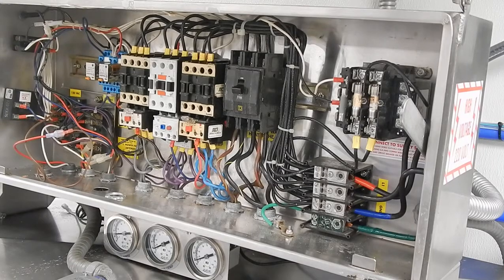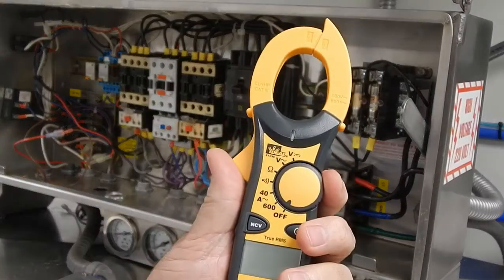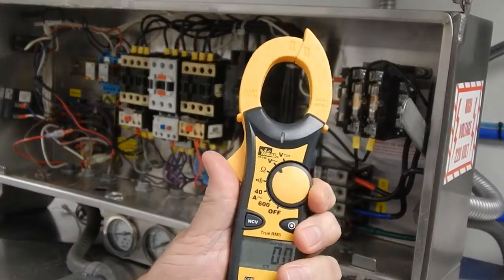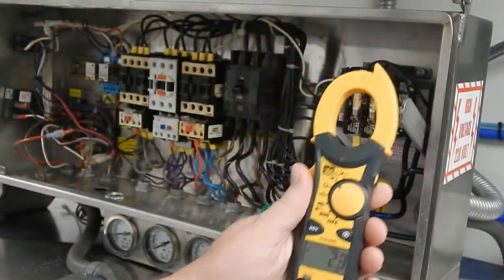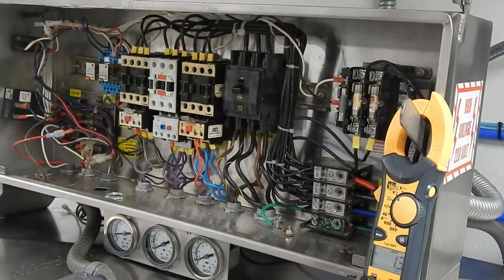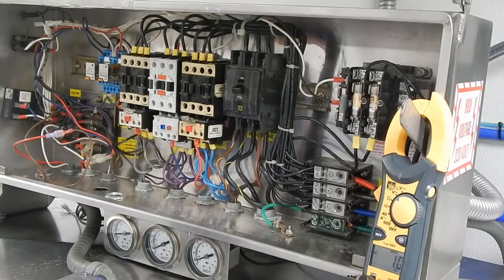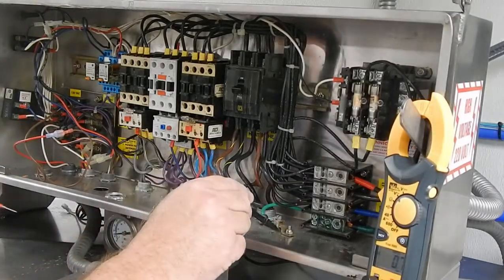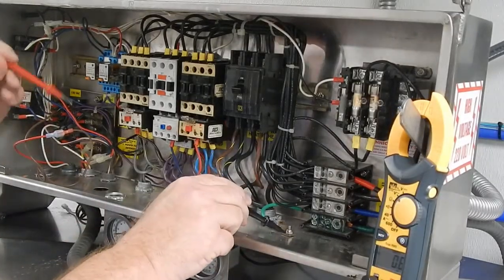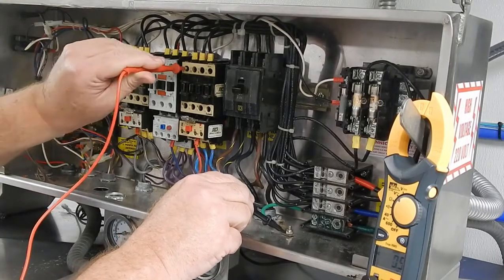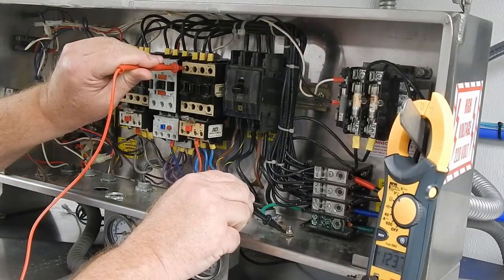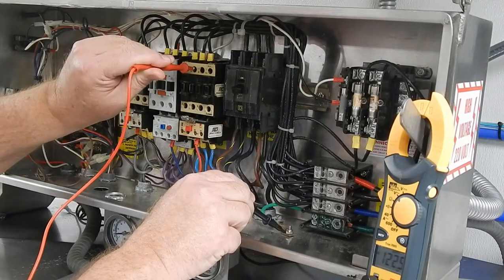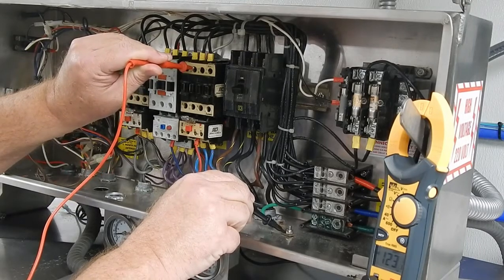First, we're going to take our multimeter. We're going to set it to AC voltage. And we're going to test our current coming into the contactor. One meter lead goes to ground. Your other meter lead goes to L1, L2, and L3. Verify that you have current coming in from main power.